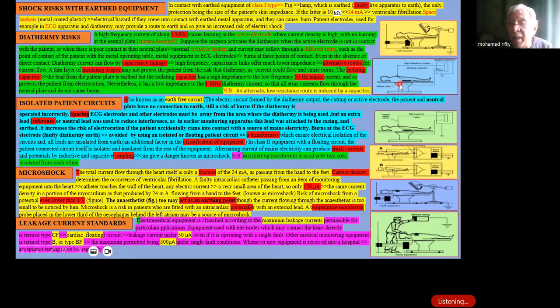So in the past equipment, we used to have what we called an isolating capacitor. The capacitor has the capability to transfer the high frequency current that is present in diathermy and not transferring the 50 hertz current of the alternating current. So we are creating an alternative pathway. So this is a method to avoid electric shock by using what we call the isolating capacitor. See, this is the equipment which is earthed with no capacitor. This is the capacitor which creates an alternative way, thus protecting against the hazards of electric shock. But we must assure that the neutral plate is being placed in a proper situation.